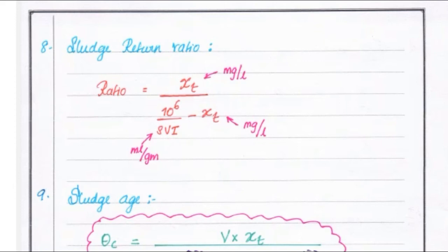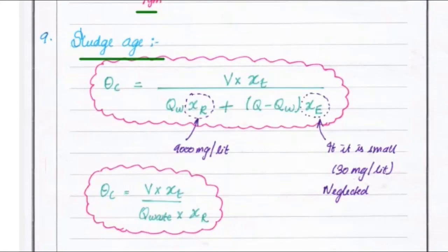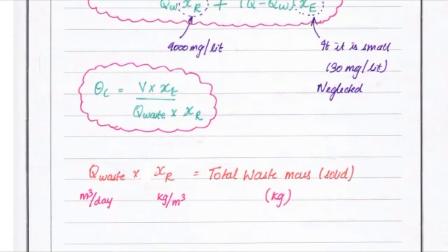Next is the sludge return ratio, which equals XT in milligram per liter divided by 10 to the power 6 divided by SVI, where the unit of SVI is milliliter per gram and XT is milligram per liter. For sludge age, theta-C equals V into XT divided by QW into XR plus (Q minus QW) into XE. Here XR equals 9000 milligram per liter and XE is small, about 30 milligram per liter, so XE can be neglected. Thus theta-C simplifies to V into XT divided by Q-waste into XR, where Q-waste in meter cube per day into XR gives total waste mass.